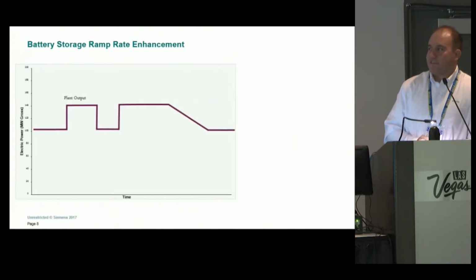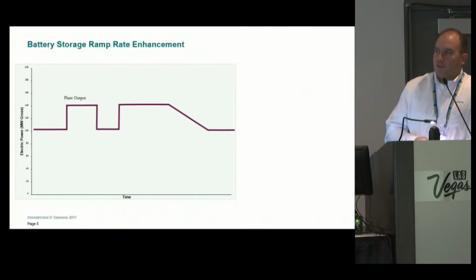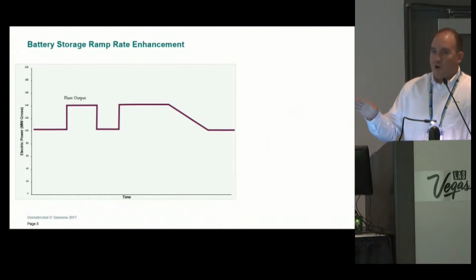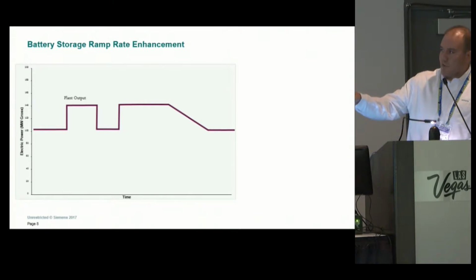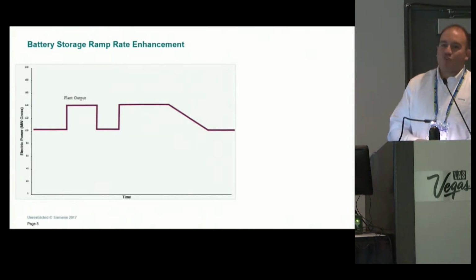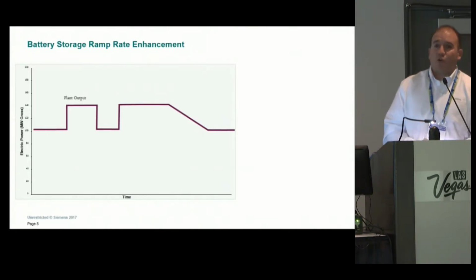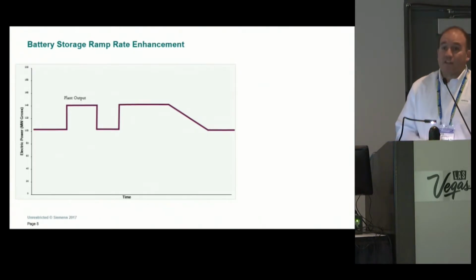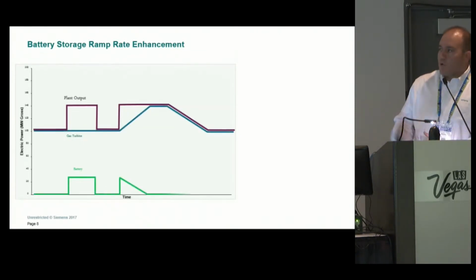Again, this is time on the x-axis, and on the y-axis is plant output, so you don't have to read any of the numbers. But in this particular scenario, the grid is saying to this combined cycle plant, here is the output that I need from you on this time scale. Now, there is no combined cycle plant installed and operating right now that can do this. There is no combined cycle plant in development that can do this, that can ramp instantly by 10, 20, 30, 40 megawatts. But batteries can. Batteries can go from no load to full load in less than 1 second. 250 milliseconds, to be precise, is what we use for it. So now when you start to say, I want this ability, how do I get this with my combined cycle plant? The answer becomes, well, you can slap a battery on it.